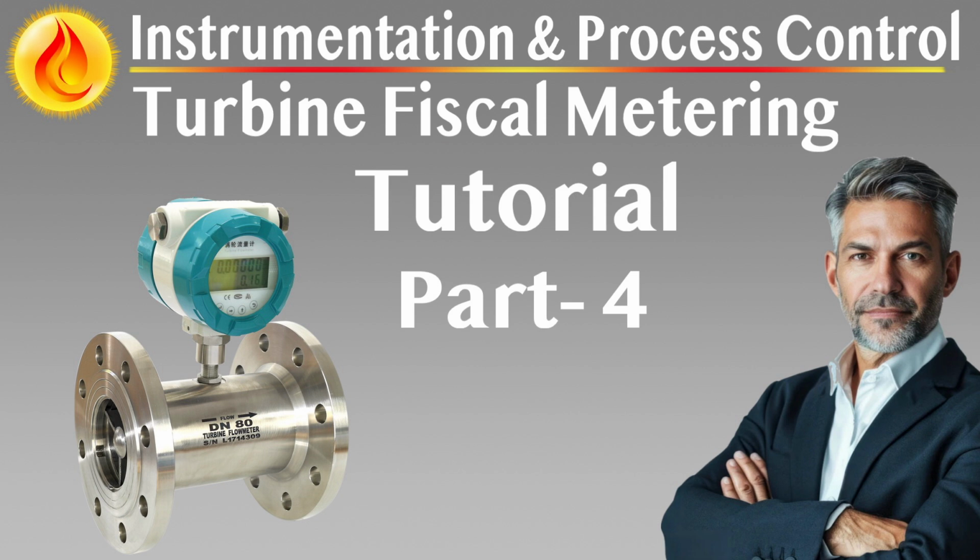The gravitational constant at the site location must be calculated for pressure calibration accuracy using deadweight testers. Reference standards must have valid calibration certificates with measurement uncertainty no greater than 1/3 that of the instrument being calibrated.